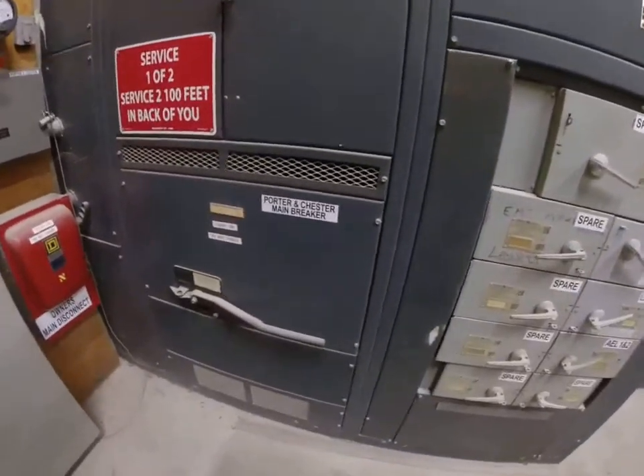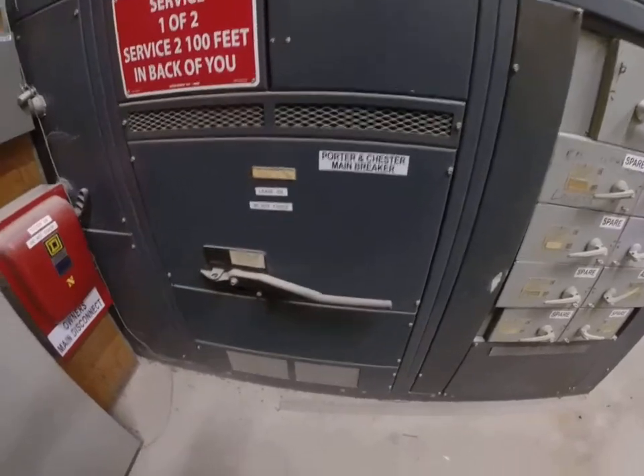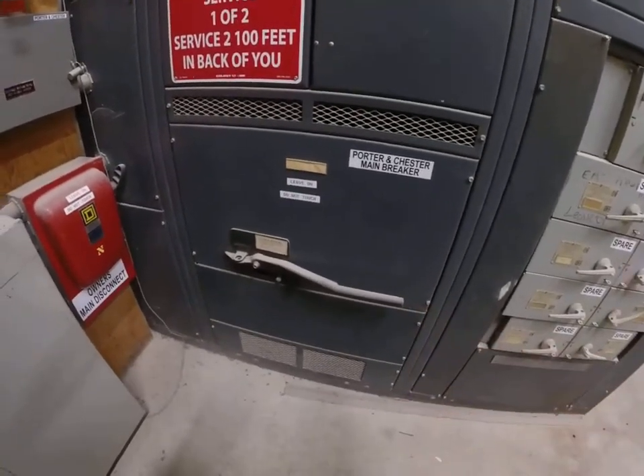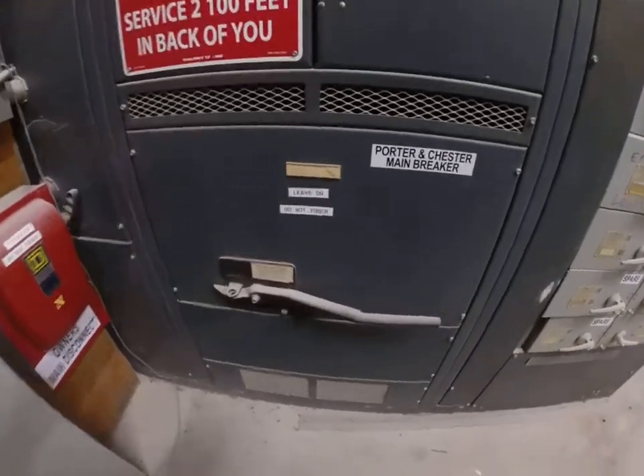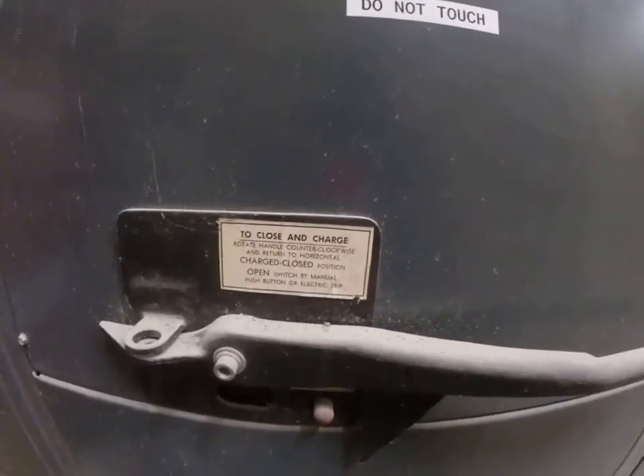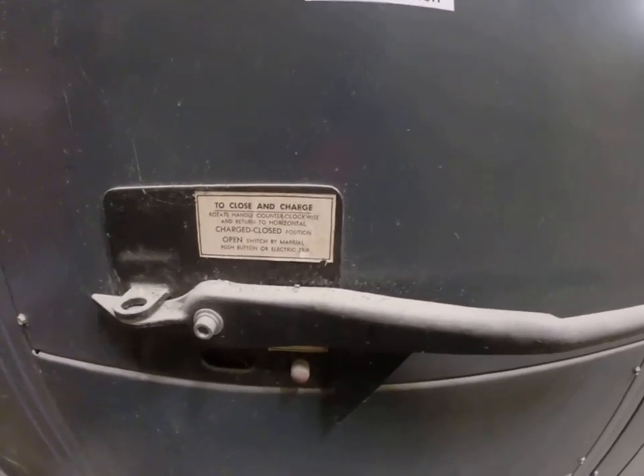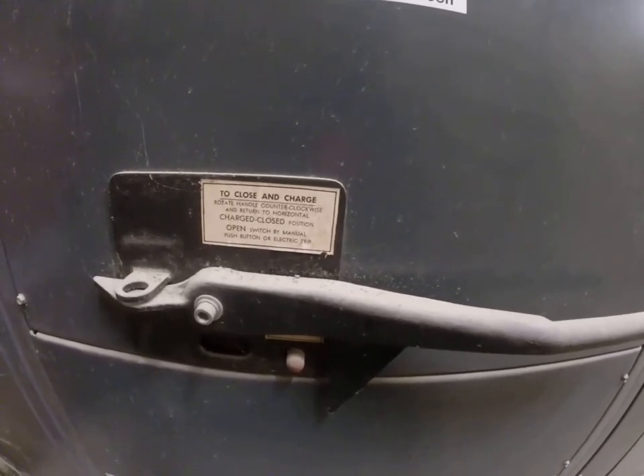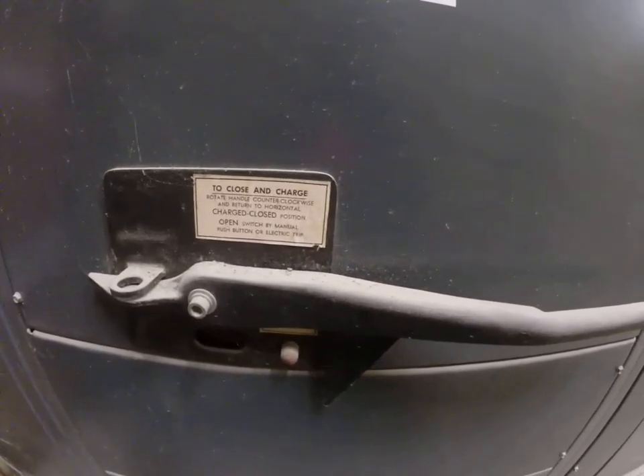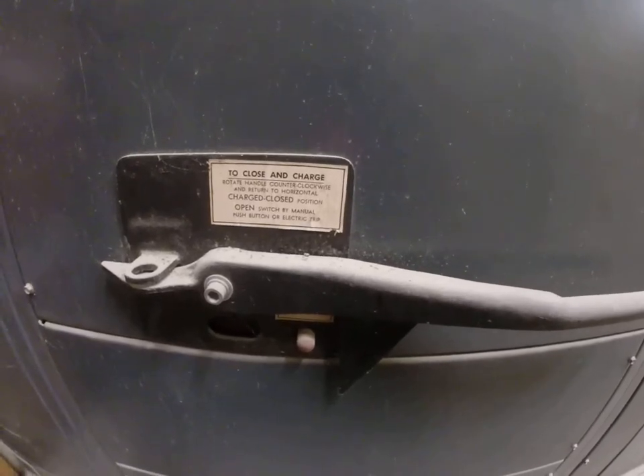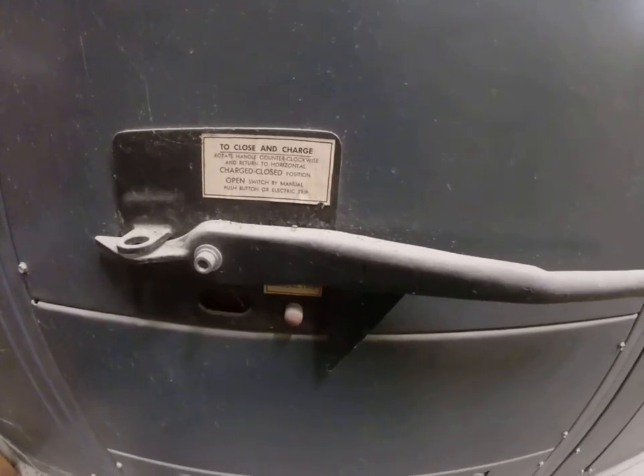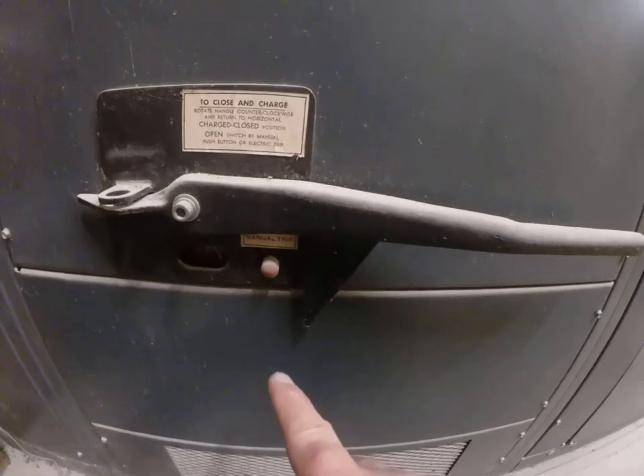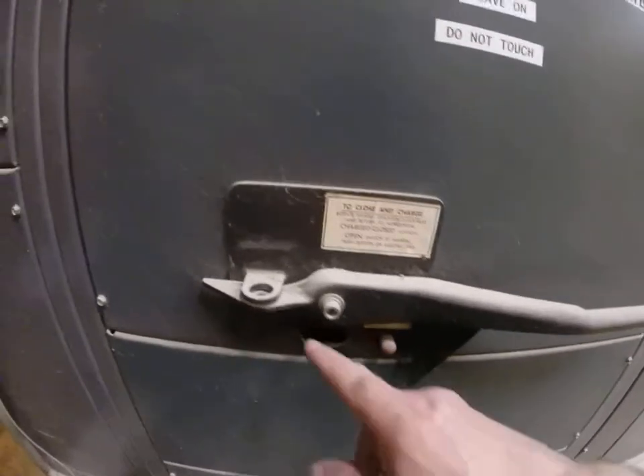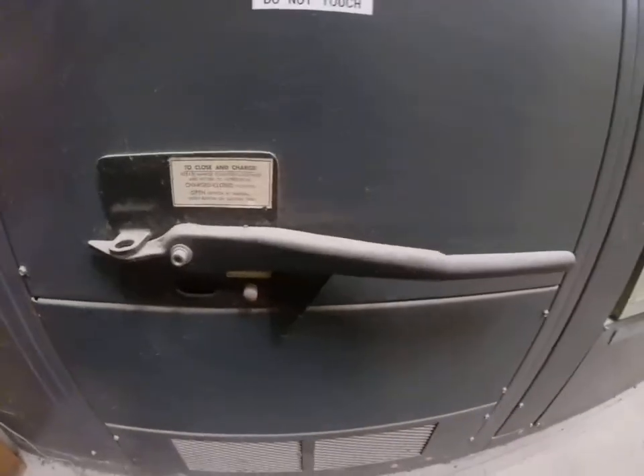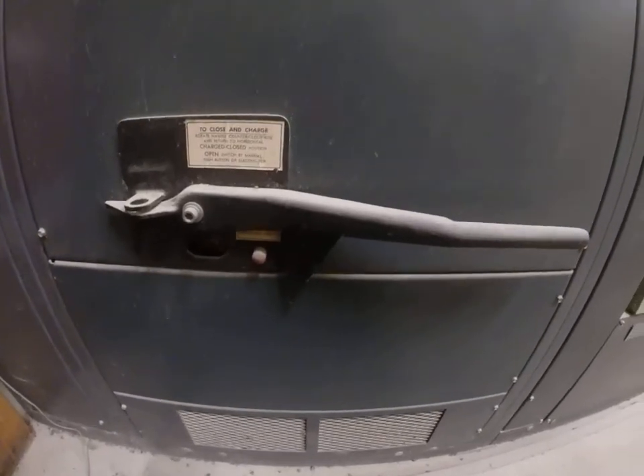Down at the bottom, you can see that it's labeled Porter & Chester main breaker, and it doesn't look like a circuit breaker. It's got a handle, and you can notice at the bottom over here it says, to close and charge, rotate handle clockwise, counterclockwise, and return to horizontal position. Charged, closed position. Open switch by manual push button or electric trip, and there's your push button. Here's your lockable means. We're gonna lock that out. So we could dump power to the whole building with that one little switch.